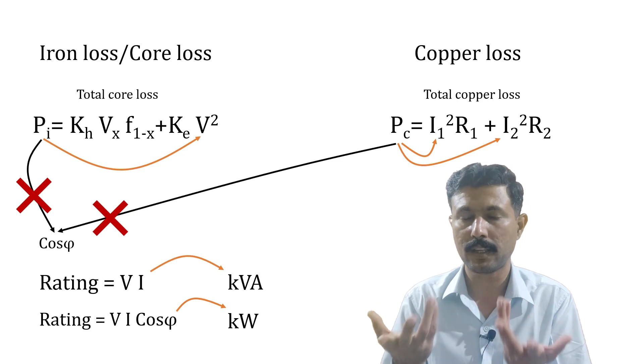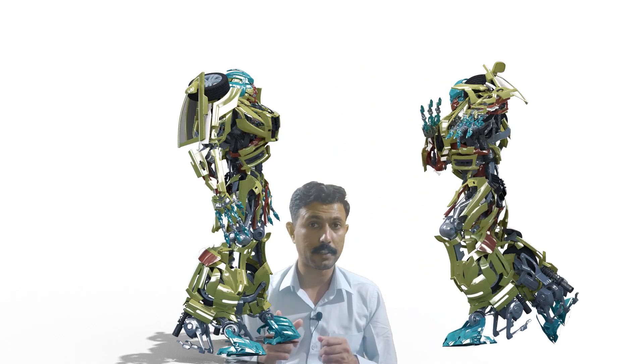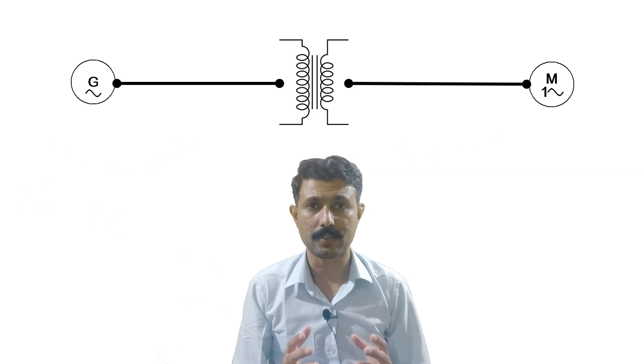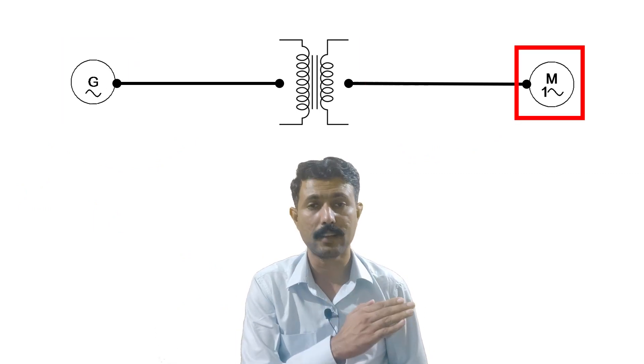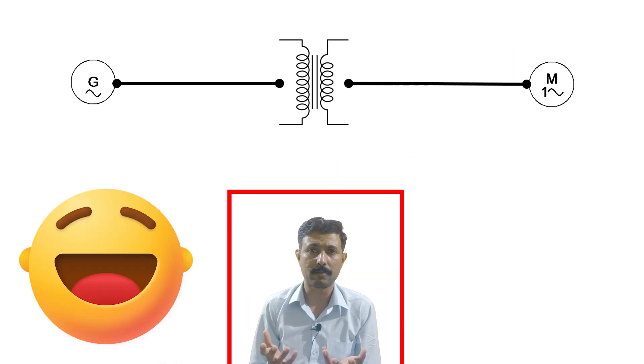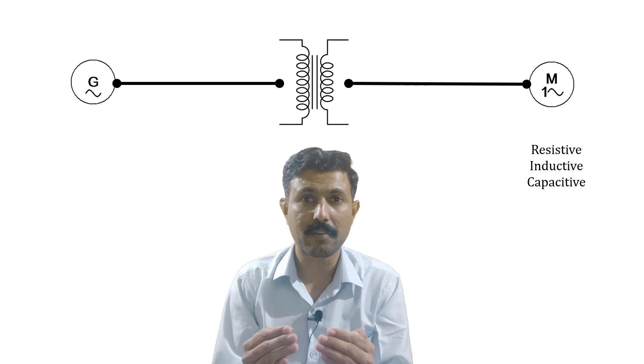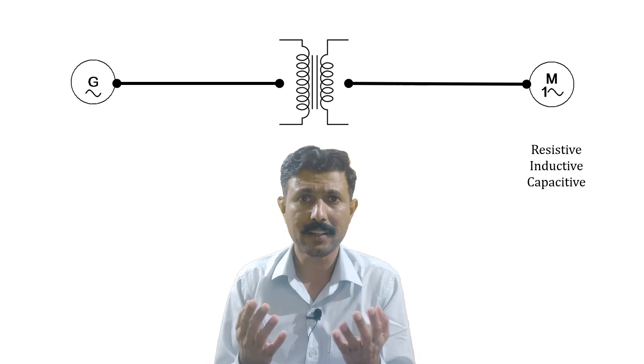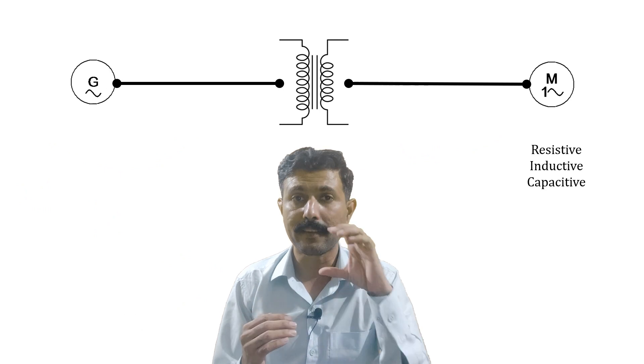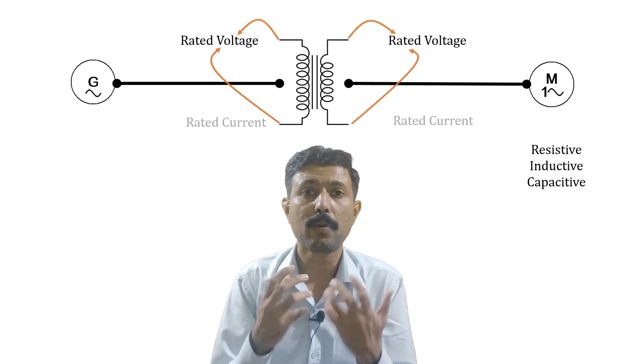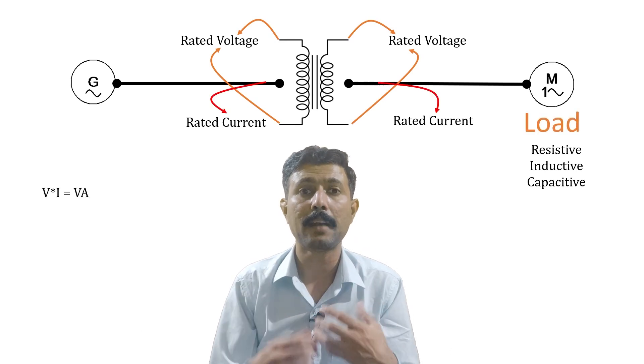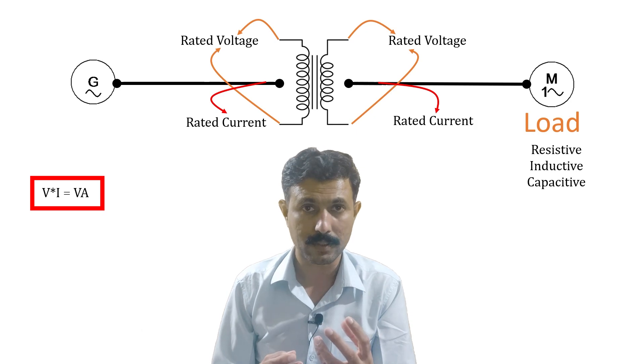The transformer is rated in VA, KVA, or MVA. Now here is another — more appropriate — explanation. Consider a single-line diagram of a power system: generating station, then the transformer, then the load. As a manufacturer of the transformer, I am not aware what type of load will be connected to my transformer. The power factor of the load is completely unknown to me. So I will decide the rating based on the information I have: the rated voltage and the rated current. I multiply them to get the VA rating.